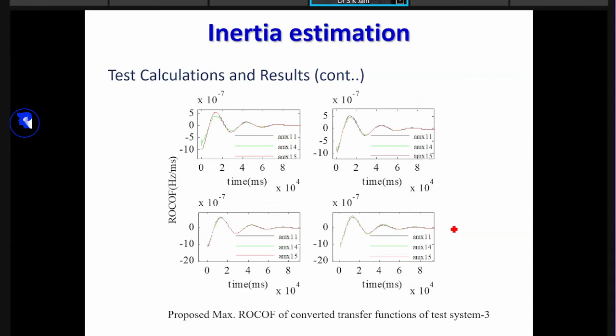How can we summarize the inertia estimation? The equivalent inertia of the power system can be estimated using PMU data for online applications. The measured dynamics of the frequency and load profile under normal operations are used for identification of the transfer function. First step, whose selected step response data is used to estimate the inertia and corresponding maximum rate of change of frequency. And this discussed method can be useful to power system operators in decision making with varying inertia due to grid tied renewable energy sources.